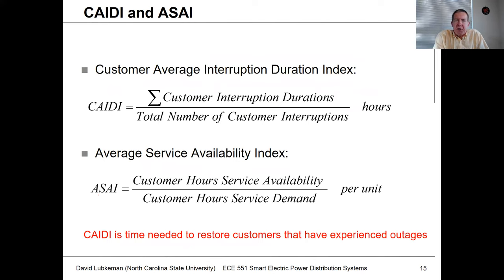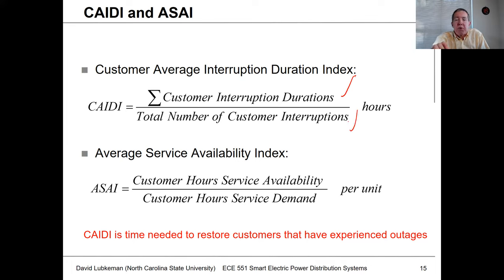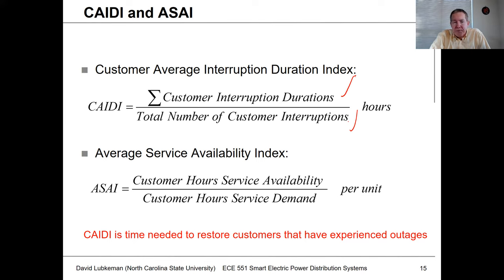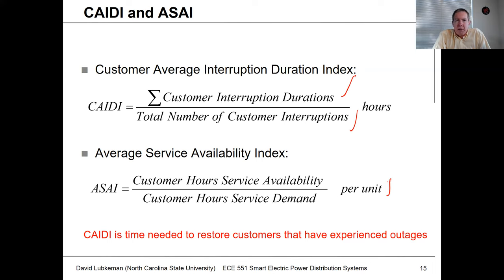Another number used by utilities is CAIDI — Customer Average Interruption Duration Index. For those customers who have an interruption, you look at the total amount of time they're out and normalize by the number of customers interrupted. This essentially measures the response of the utility to fix the problem — a CAIDI of two hours means customers with an outage can expect to wait two hours on average. There's also ASAI — Average Service Availability Index — which is a kind of availability number, though it's not used as frequently.